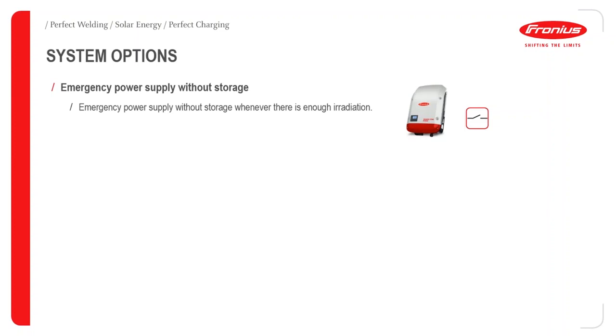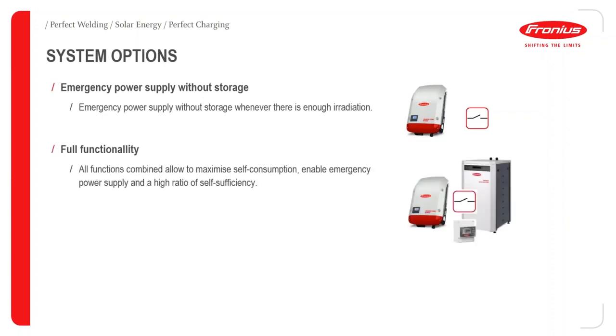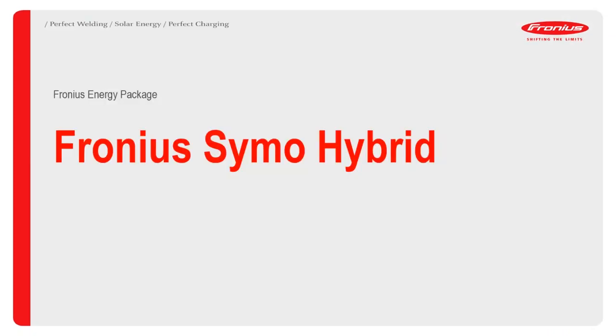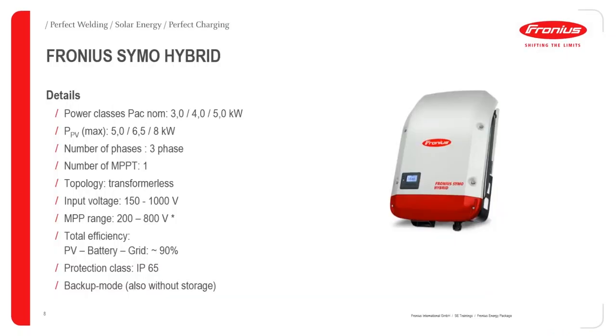When it comes to the emergency power supply, the backup function, which will be available mid-year, around June, July this year, what that is: if the grid goes down, the inverter will disconnect from the grid through an external contactor and start up in island mode and provide power when the grid's down. It can actually do that without the battery too, so long as there's enough irradiation, enough sun, you can have it in backup mode even if there's no battery connected. Or if you want the full functionality, obviously with the battery connected, it makes it a more efficient and more robust option.